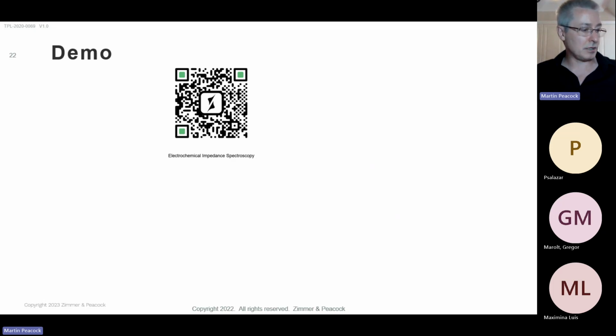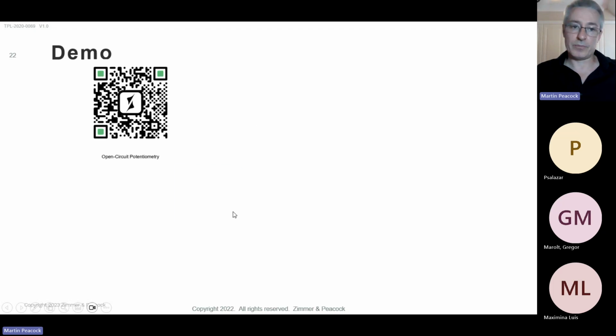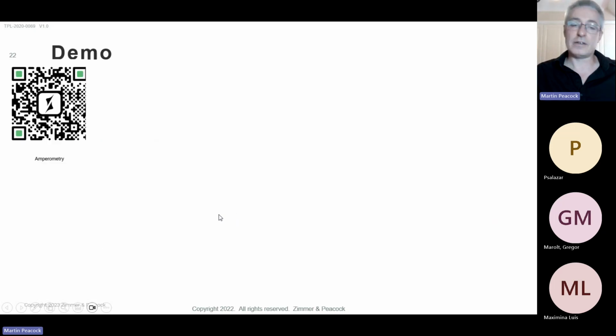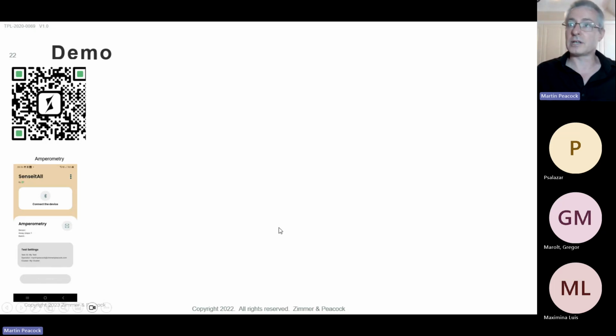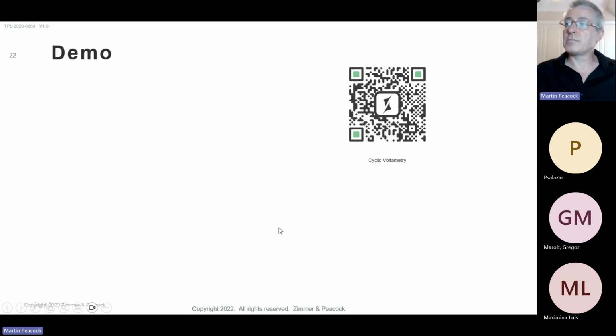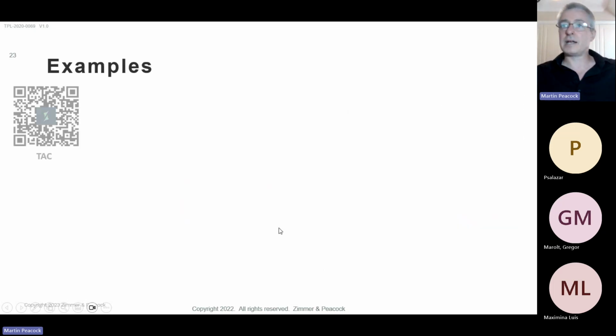Though I did see some interesting work coming from, I want to say, Northeastern University, on wearable immunosensors. And if you want to do things like ions, sodium, potassium, etc., or pH, then you probably end up using potentiometry. And if you're doing glucose, lactate, oxygen, maybe ketones, then you would end up using amperometry. So different modalities, or different electrochemical methods, for different analytes.